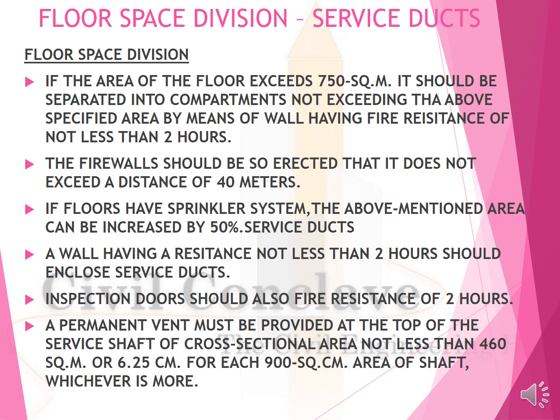Service duct. A wall having resistance not less than 2 hours should enclose the service duct. Inspection door should be of fire resistance of 2 hours. A permanent vent should be provided at the top of the service shaft, of a cross-sectional area not less than 460 square meter for each 900 square centimeter of area of the shaft, whichever is more.